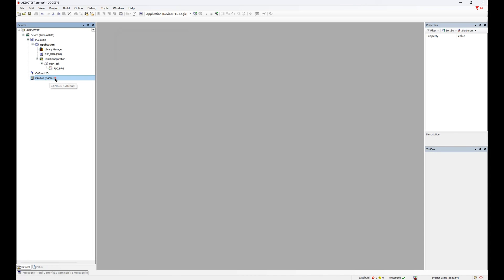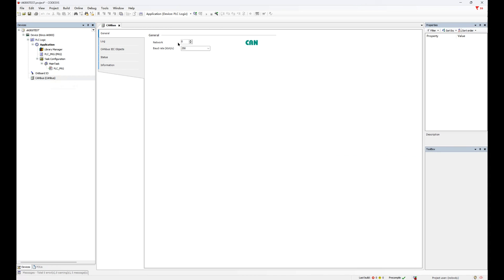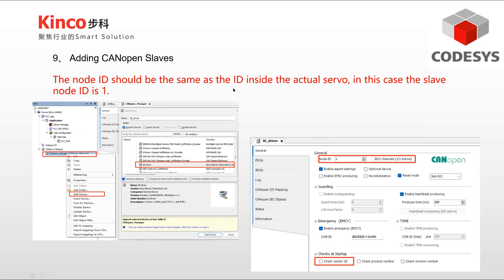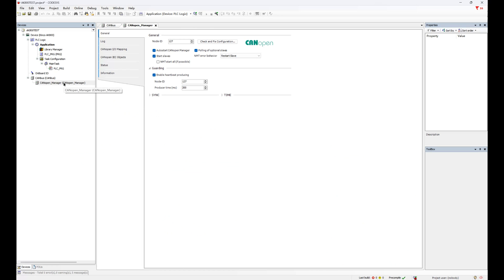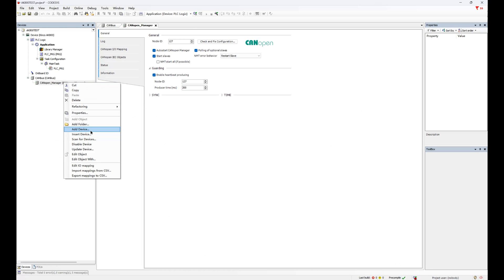The 0 and 1 in CAN bus refer to the CAN 0 and CAN 1 ports respectively. If high precision is required, the baud rate should be set high to increase communication speed and device accuracy. Next, add the driver file of the Kinco Servo. After adding the EDS, the JD driver will be automatically generated. The node ID of the JD driver is consistent with the servo — the default node of the servo is 1, so you can use the default ID. Click Add Device and you will find the JD drive.